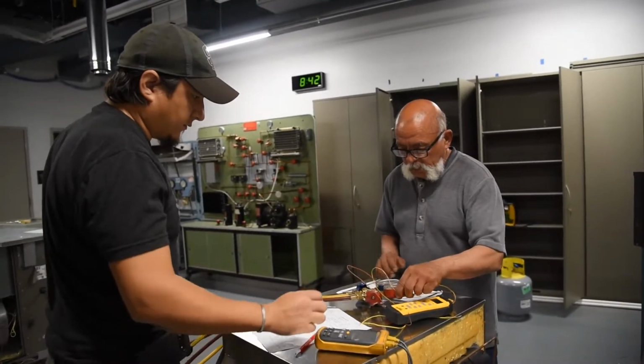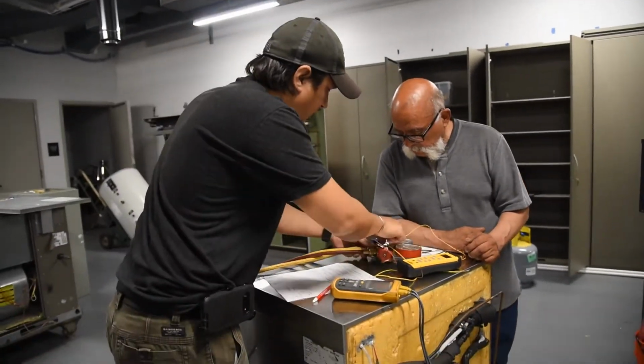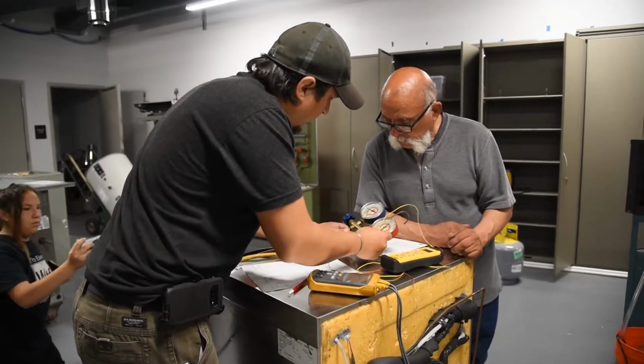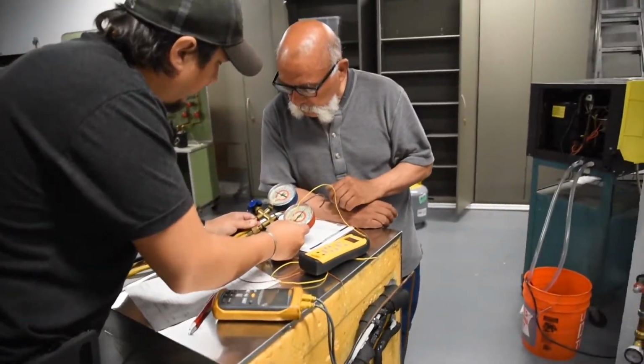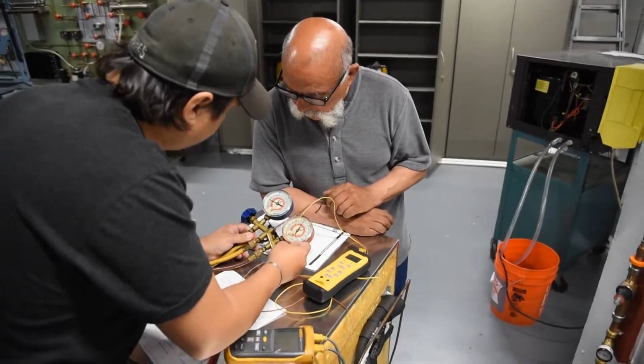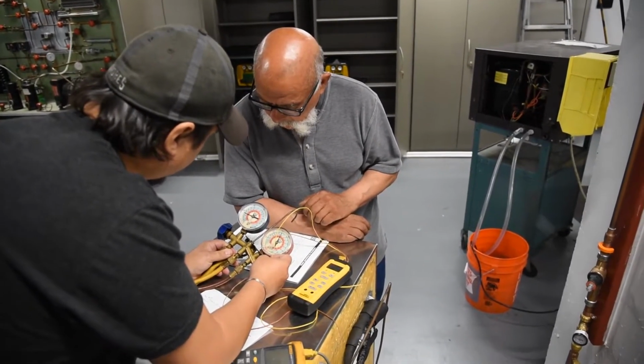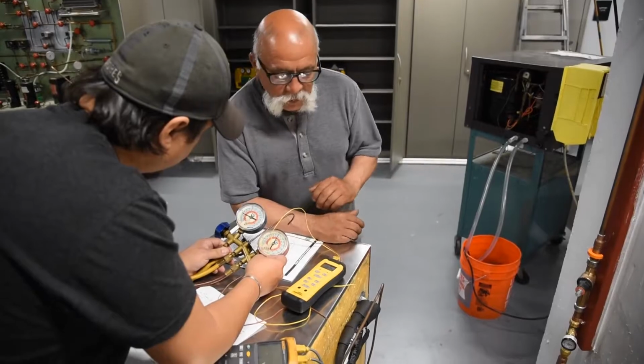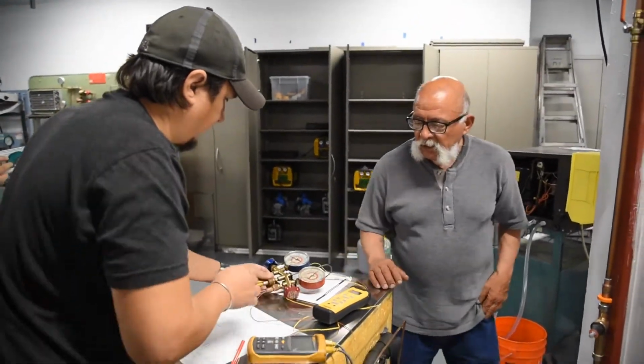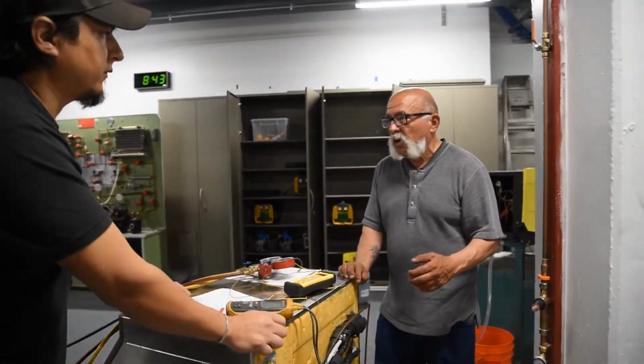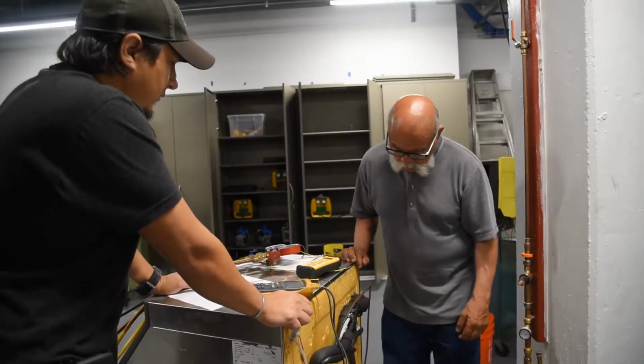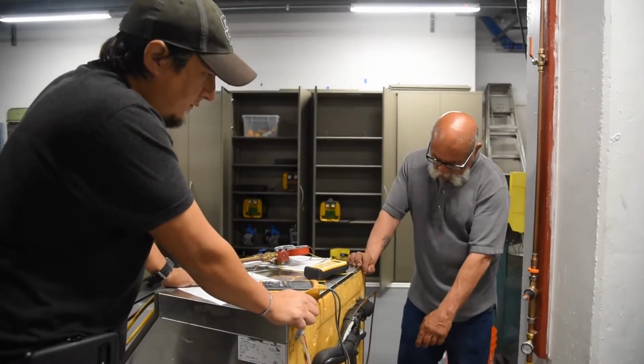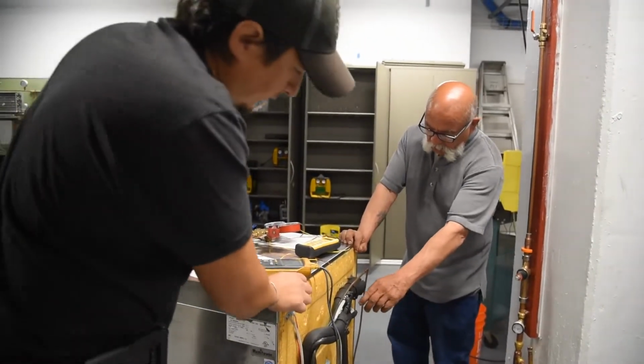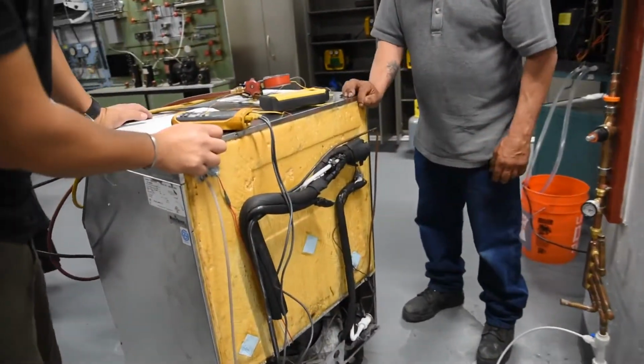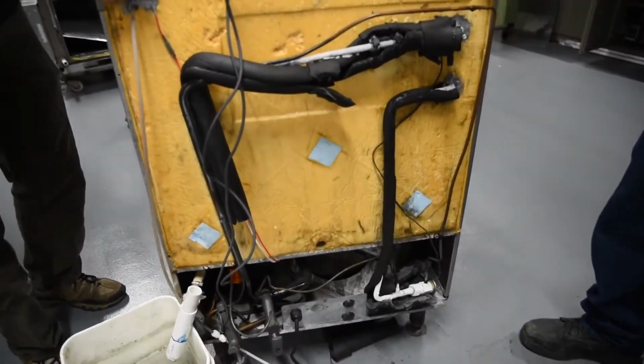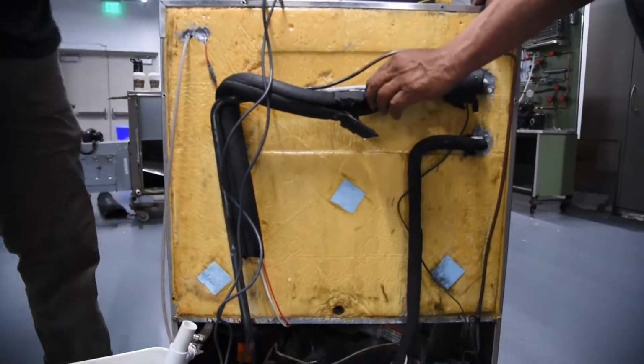What is our low side pressure now? Low side pressure is about 40. Our temperature is about 5 degrees. Okay, so the temperature is dropping because of the ice buildup on the evaporator.